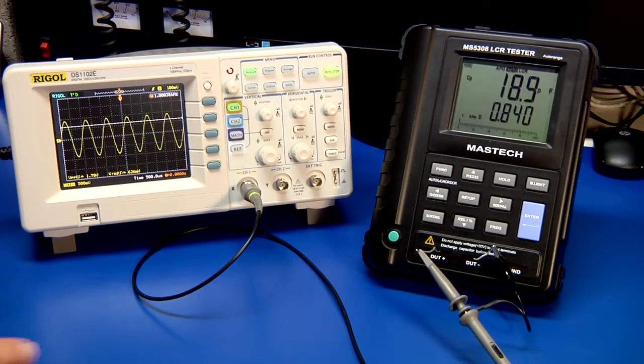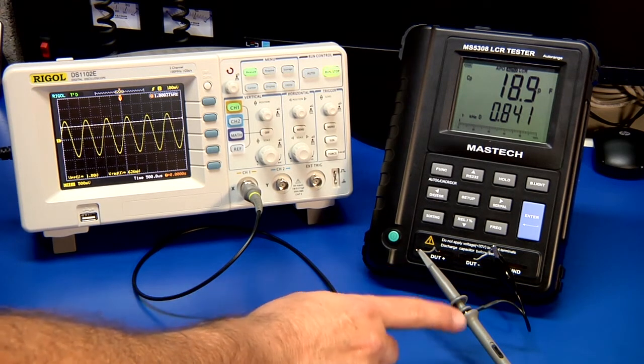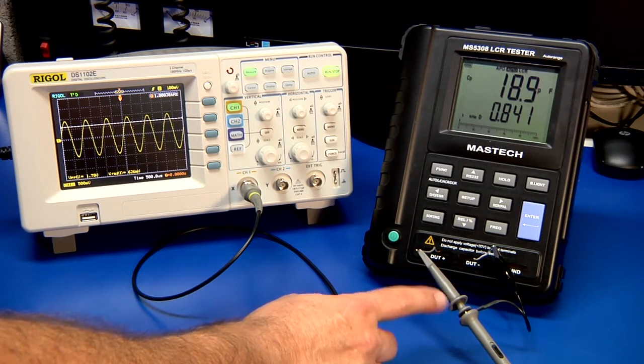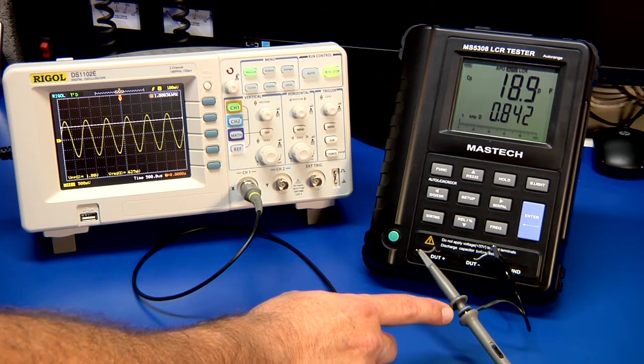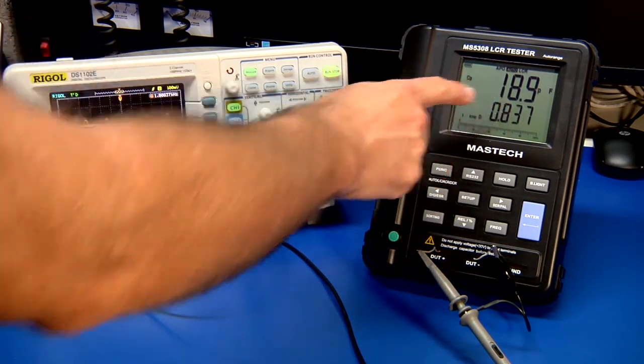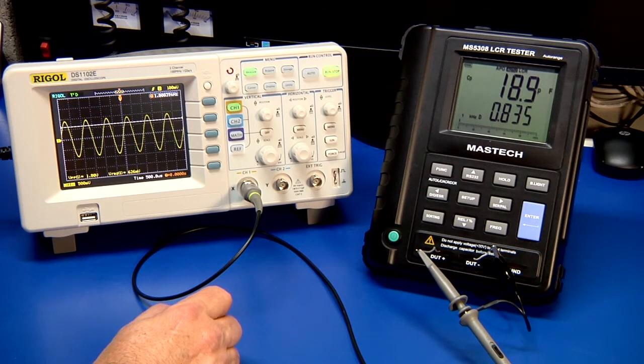In this section, I'm just checking the excitation signal coming from the tester. I have a 10 megohm oscilloscope probe with a shunting capacitance somewhere between 15 and 20 picofarads. The unit is actually reading the parallel capacitance at 18.9 picofarads.